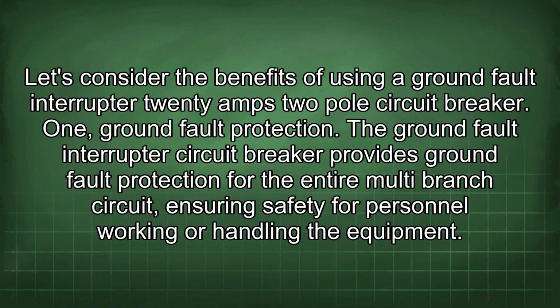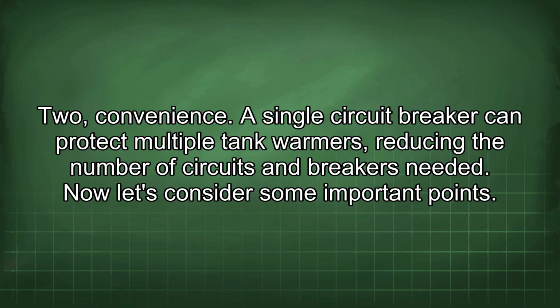Let's consider the benefits of using a ground fault interrupter 20 amps 2-pole circuit breaker. 1. Ground fault protection. The ground fault interrupter circuit breaker provides ground fault protection for the entire multi-branch circuit, ensuring safety for personnel working or handling the equipment. 2. Convenience. A single circuit breaker can protect multiple tank warmers, reducing the number of circuits and breakers needed.